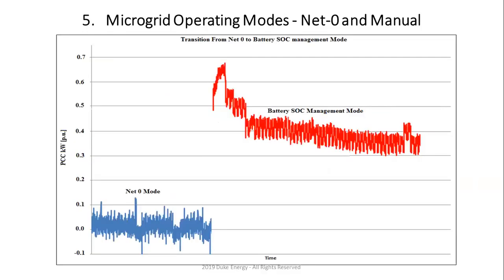So net zero mode, you can see it's the blue line over here. The reason why it's never exactly 0 is because some of these devices that you communicate with are DNP3, some of them are Modbus. So by the time you get to it, they calculate it's going to be somewhere close to 0. It's never going to be 0. Second of all, you do have to understand CTs are typically 500 to 1 or 1,000 to 1. Over here, they're 500 to 1. They have inaccuracy at the low currents. That's about 5 to 6% on the magnitude. It's somewhere about 6 to 8% on the angle, right?